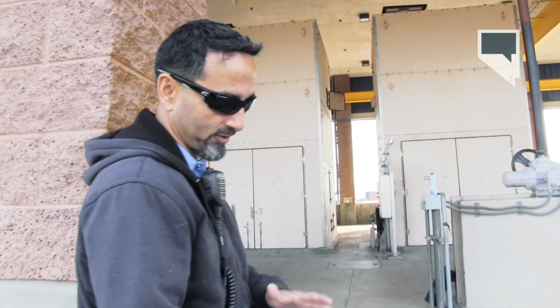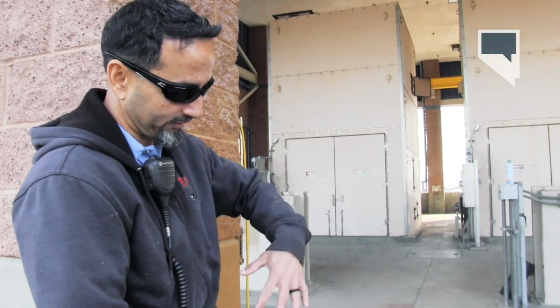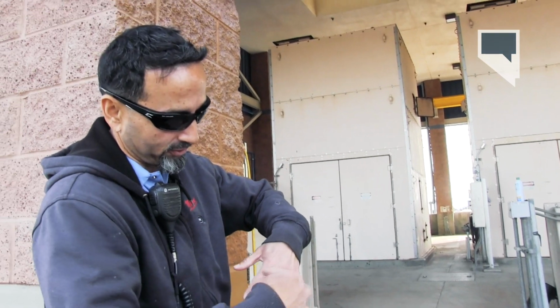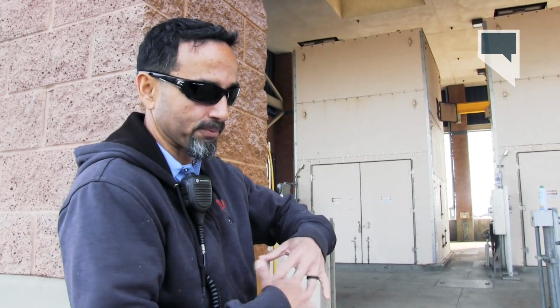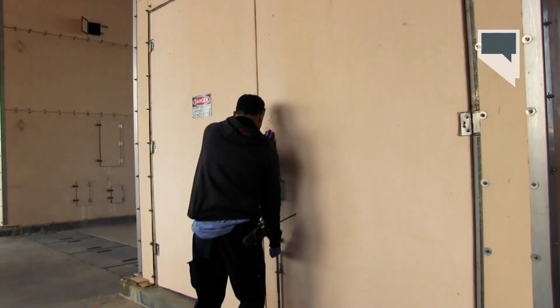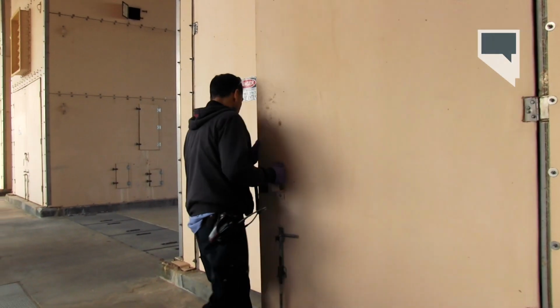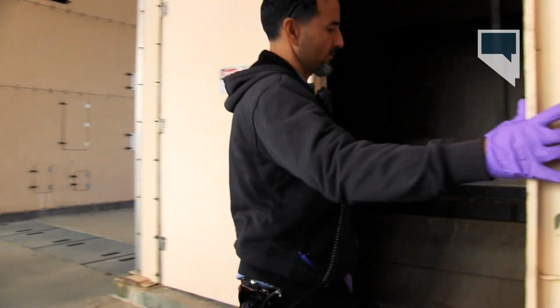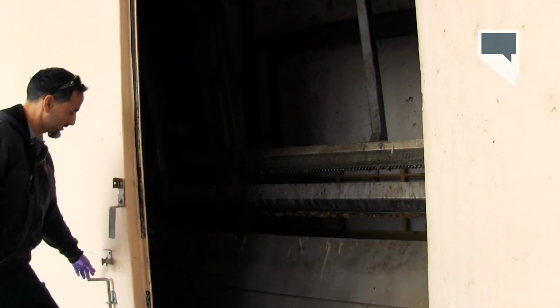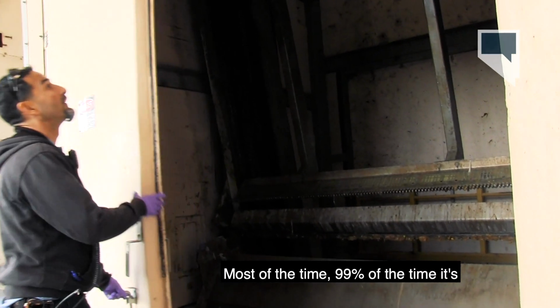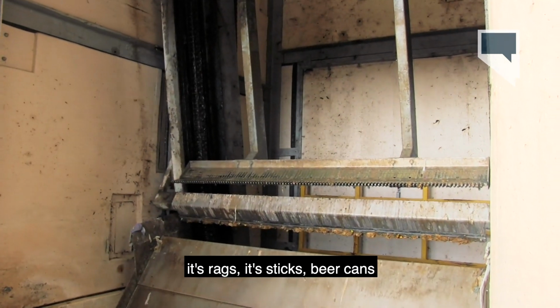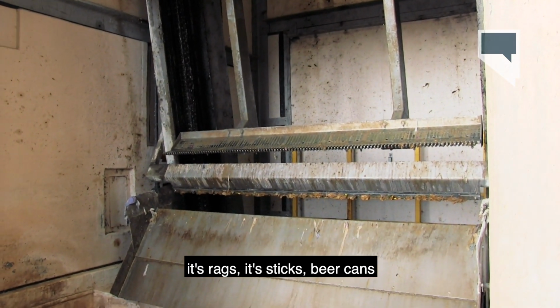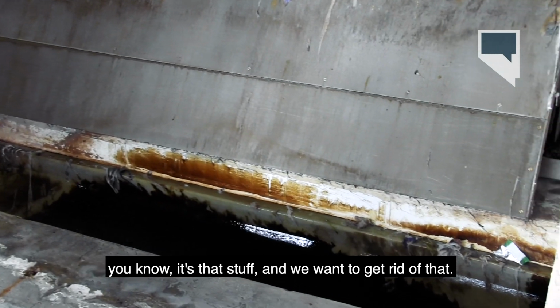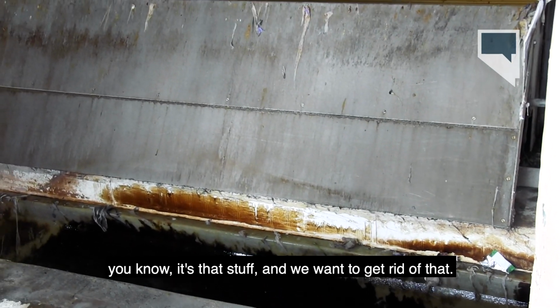The line comes in, and it goes through one of our 4 gates. And these gates are racks, and what they do is they sit down there, the flow's going through them, and any trash or debris that goes through it should get stuck on the gate, and then periodically on a timer it pulls it up and then dumps all the trash out. We try to take out as much as we can. 99% of the time, it's rags, it's sticks, beer cans, that stuff. And we want to get rid of that.